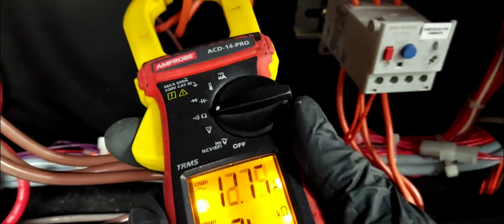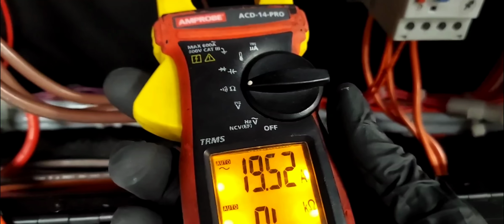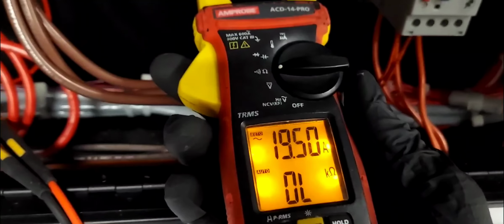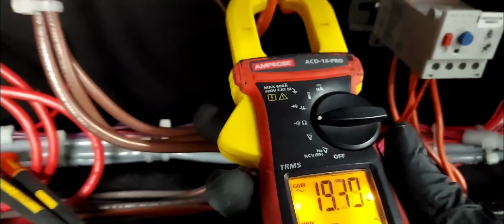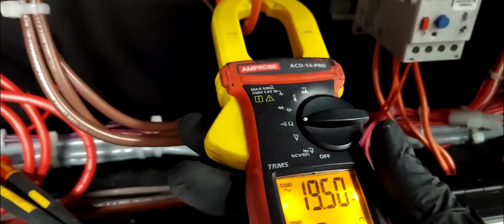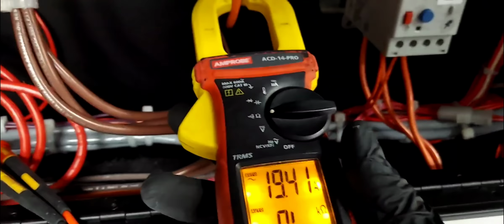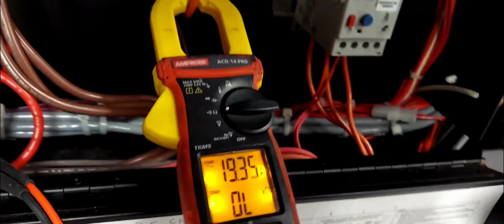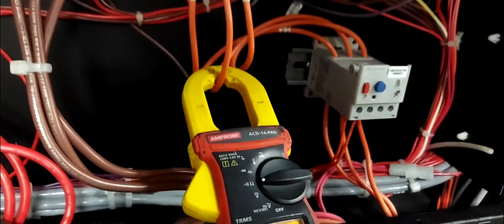I'm going to be monitoring this for about 30 minutes or so to see what happens with the amperage. And I'm also going to go grab my mega ohm meter, and I'm going to meg out this motor just to make sure the windings are in the clear. And if that is in the clear, then I'm just going to recommend to replace this motor overload. That's going to be the diagnostics, and that's going to be the recommendation.